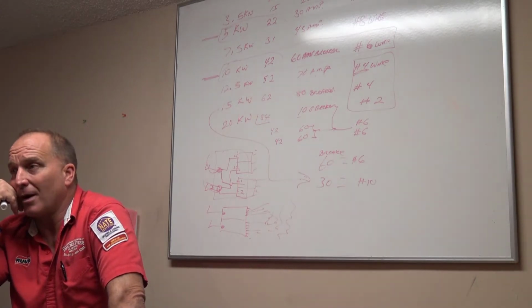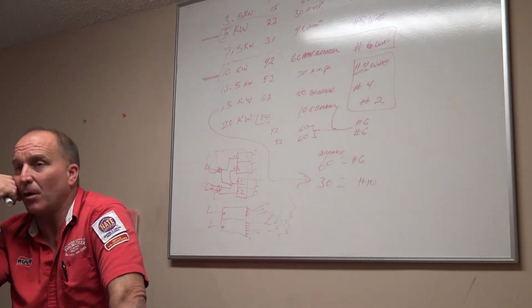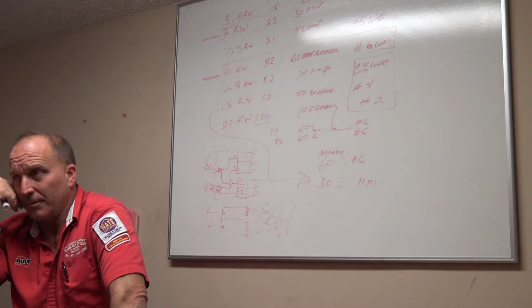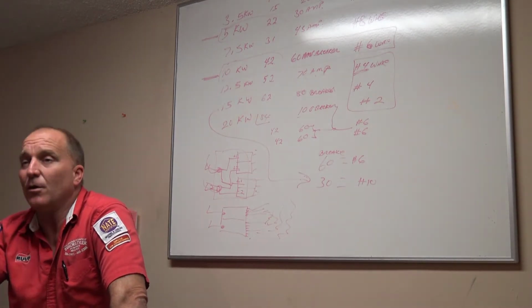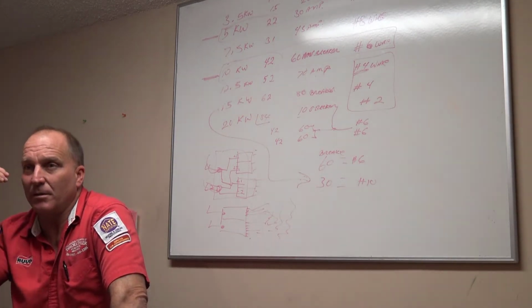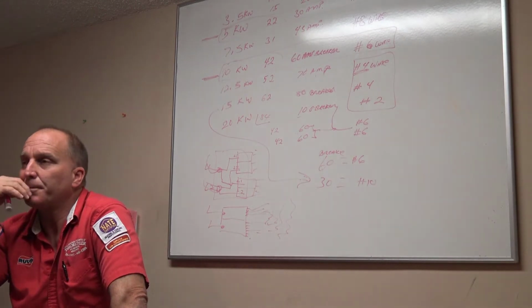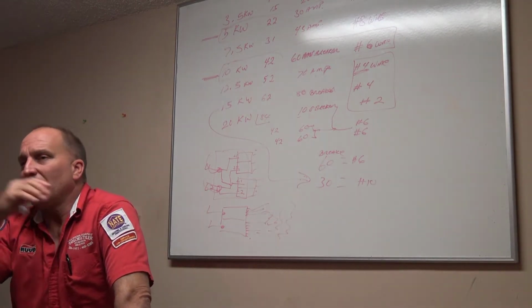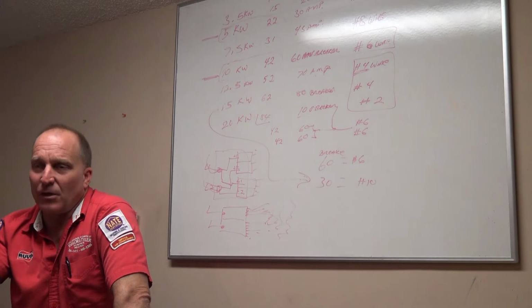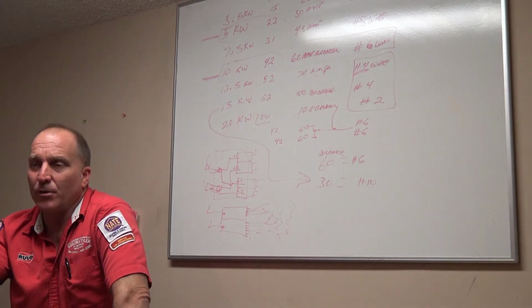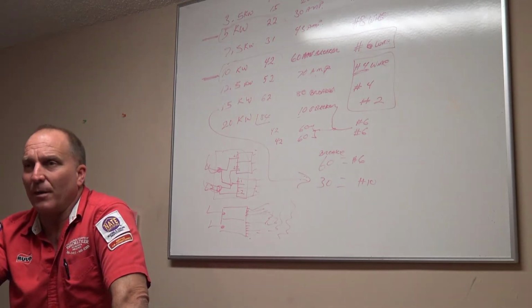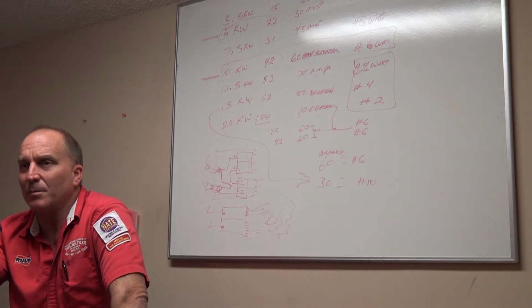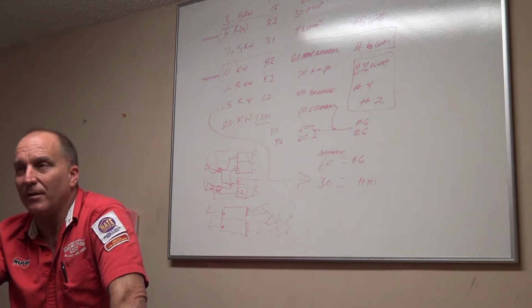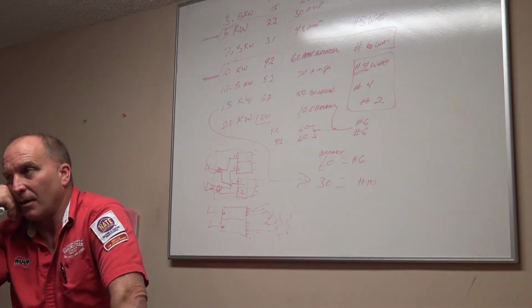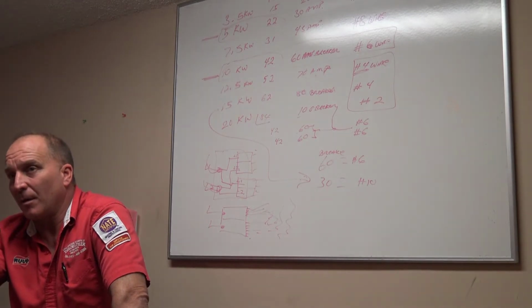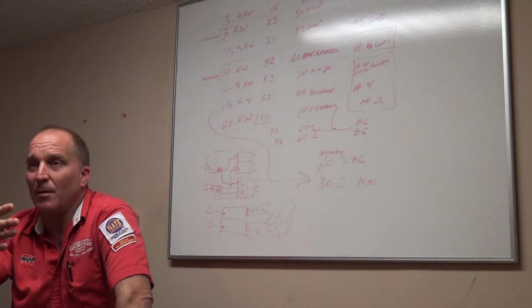If you got burnt wires, then stop. You need to tell them you need to replace these burnt wires. Don't go any further. Replace the burnt wires and then you go from there. Okay, or fix the disconnect box or whatever it is. So let's just say all that looks good. Then you turn your heater on, you put your amp probe on it, and I want to make sure that your heater actually comes on before you do anything to this system. Okay? Does your heating element come on, or does your gas furnace come on?